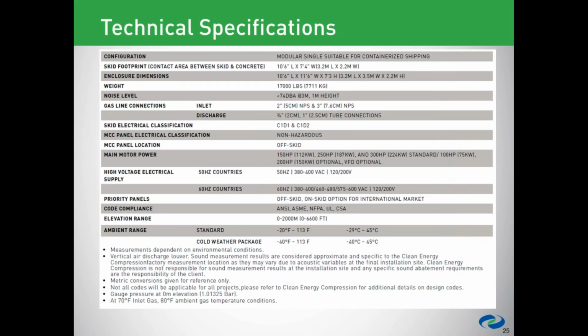So, well, I can speak a little, and something I forgot to mention about the cooling system is because of the efficiencies we've gained in the cooling, in many cases, what we've implemented is what we call eco mode in these units. There's a thermocouple mounted in the discharge line of the final gas, and if that temperature gets well within the target temperature of the cooling, we can actually turn off one of the cooling fans to save energy. And so what we'll see often is there'll be one fan that'll turn on for, say, 5 minutes, and then it'll turn off for 5 minutes.